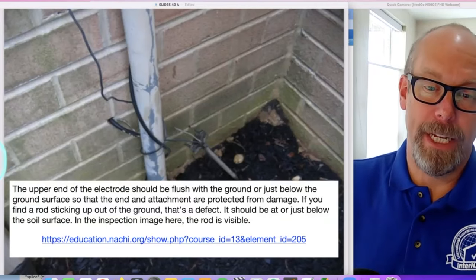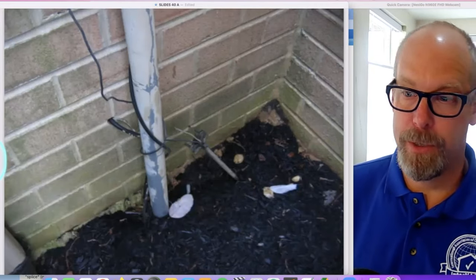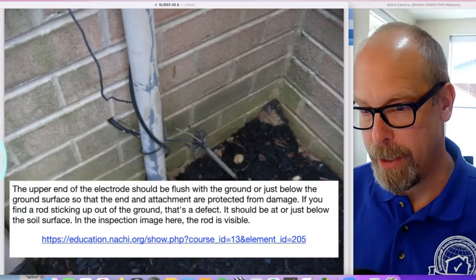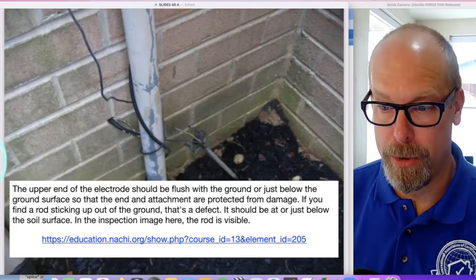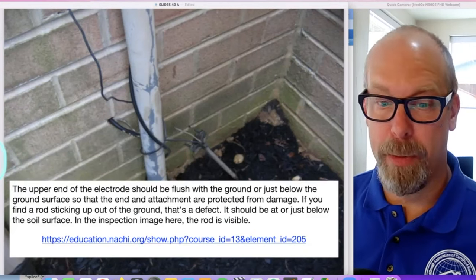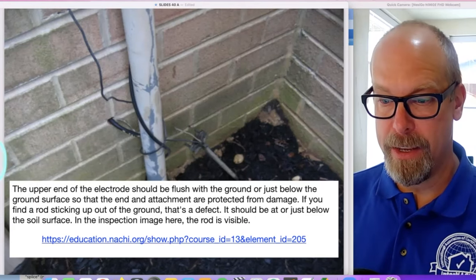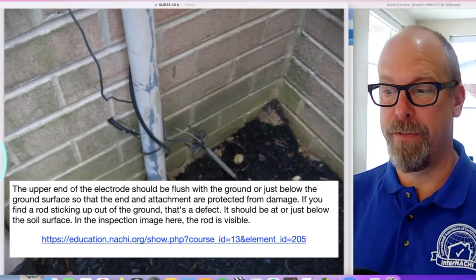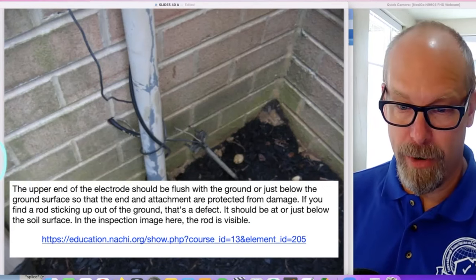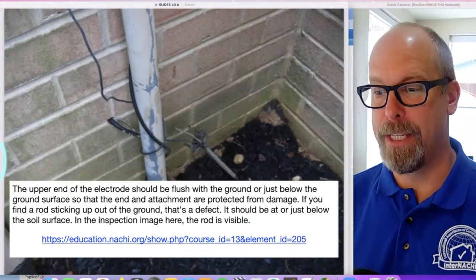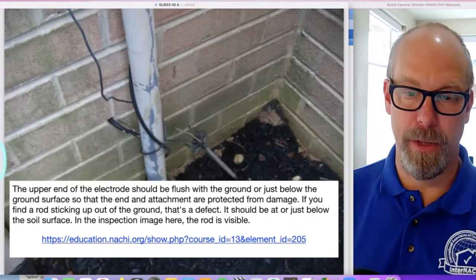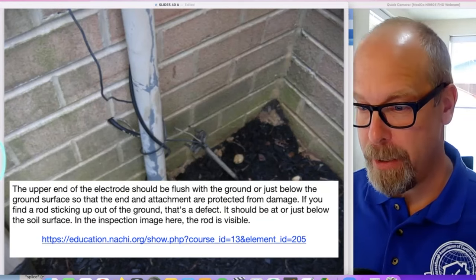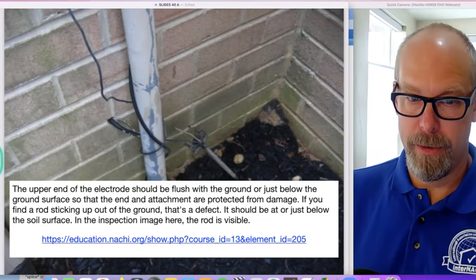There's certain things I just can't see. And there's the rod there for grounding. The upper end of the electrode should be flush with the ground or just below the ground surface so that the end and attachment are protected from damage. So if you find a rod sticking up out of the ground, that's a defect. It should be at or just below the soil surface. In the inspection image there, the rod is visible.